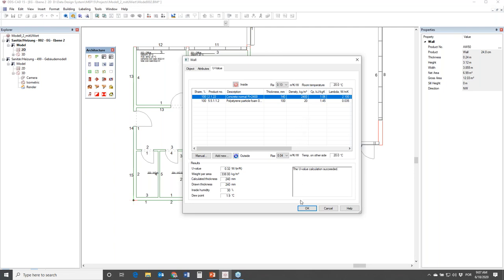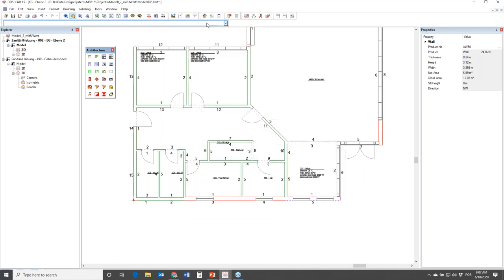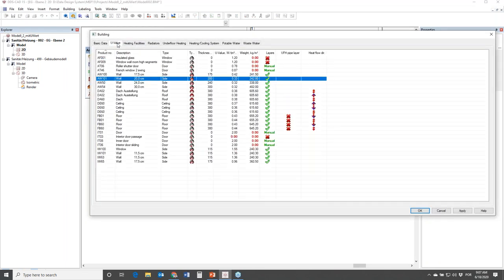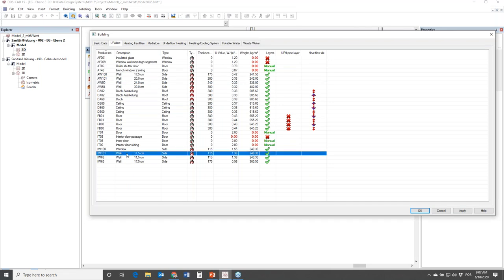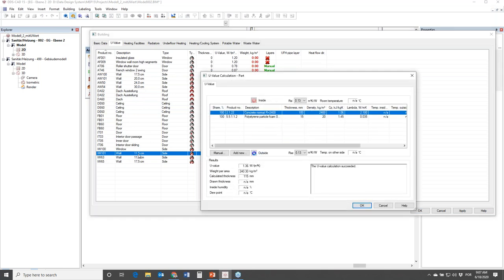If we do it one by one it will be a lot of work. In DDS-CAD we can go to the building function, then in the U-value tab we can see all the building components for the complete building. If I double-click wall 100 of 11.5 centimeters, I will be changing and mapping all the walls with these properties on my complete building, making it a much faster workflow.